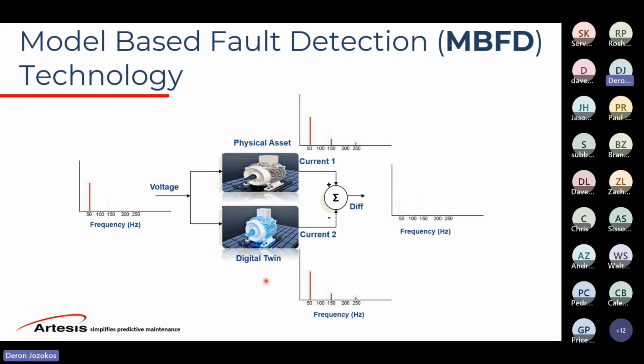The EMCM, when it's installed, creates a digital twin. I know that's a big buzzword in the AI world today, but we truly create a digital twin. This is how our system has always worked. We put in the motor nameplate information, so it's creating a healthy asset of that particular machine. So whether it's a brand new motor or a 20-year-old motor that's got some faults and really on its last leg, it doesn't matter. We create that digital twin, we duplicate that motor, right?